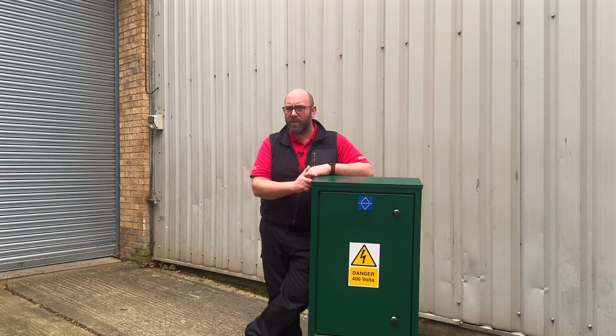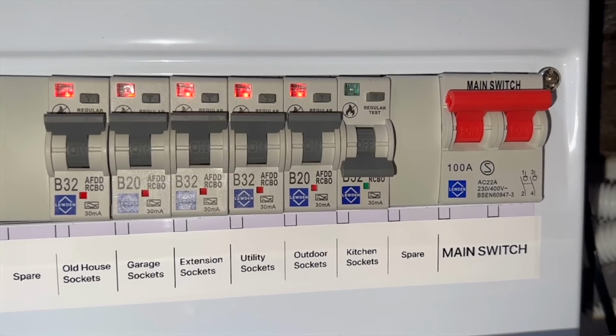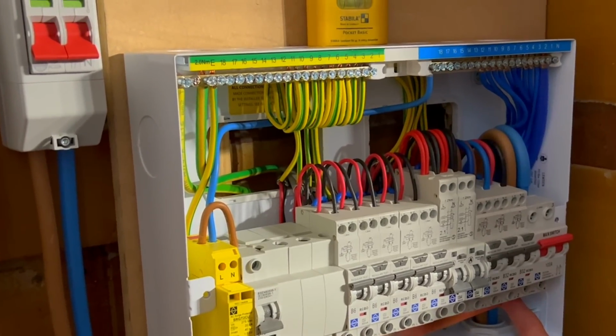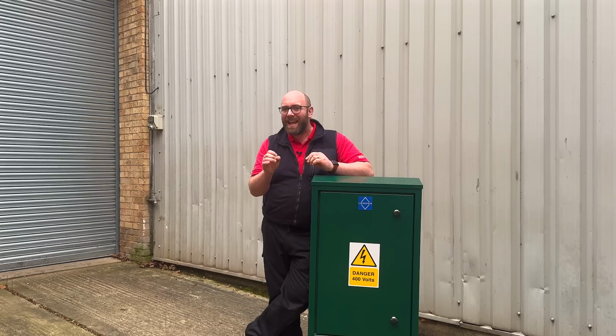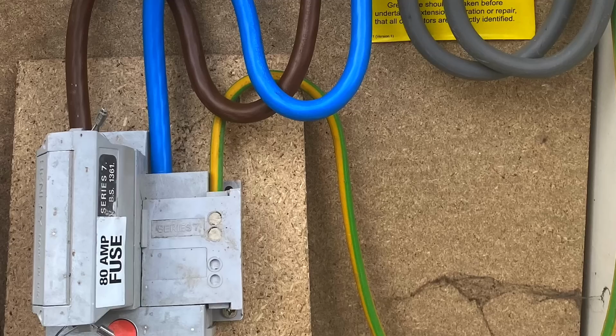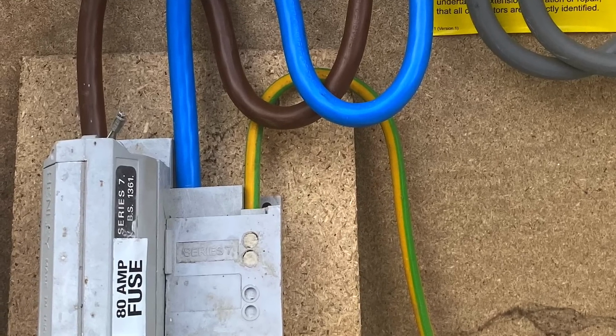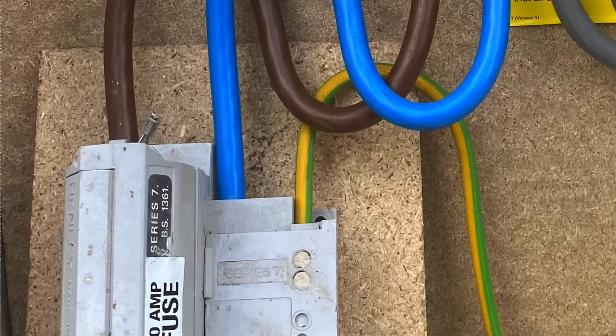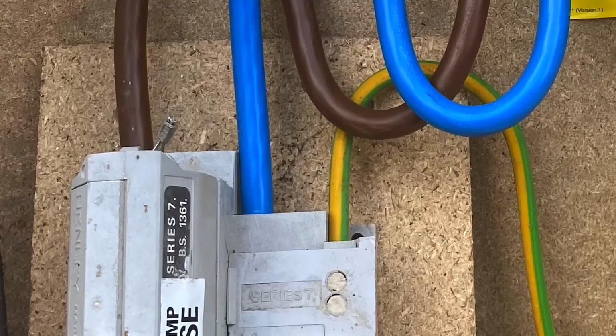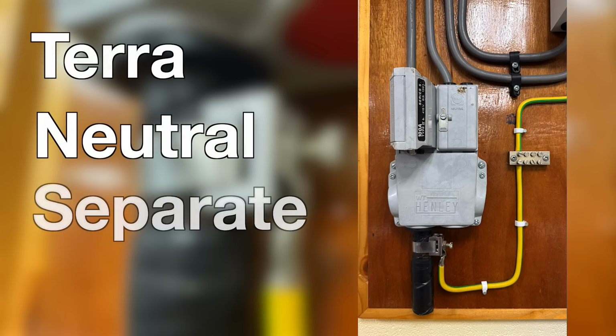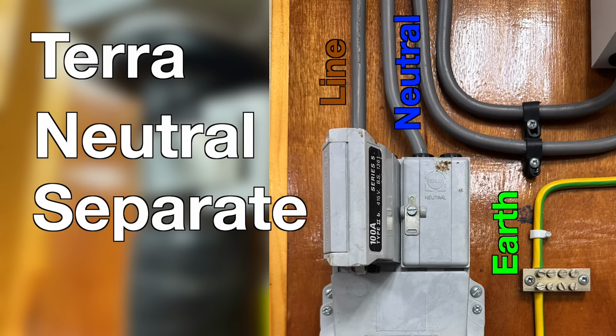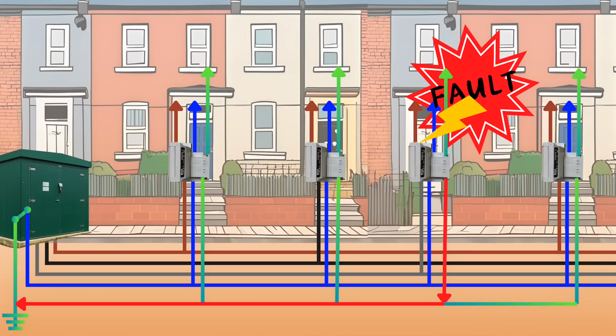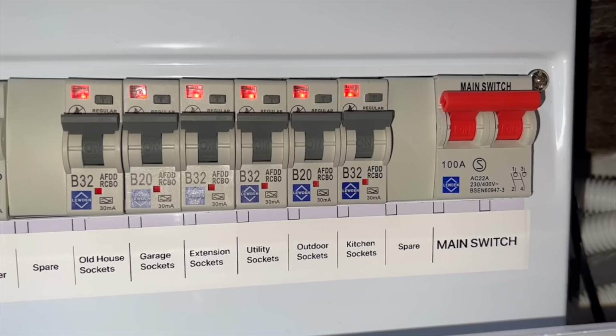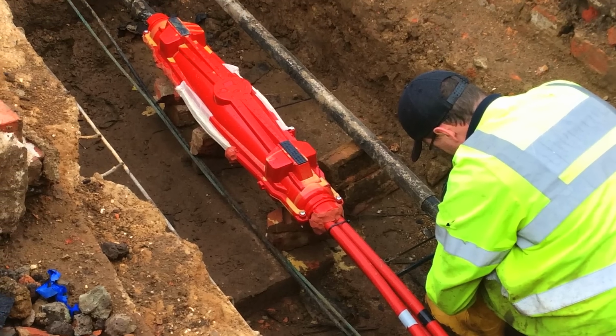This separation is crucial for safety because it ensures that any fault current can safely flow to earth without carrying a risk of running through the neutral. The TNCS system provides an efficient, effective way to protect homes and installations from electrical faults, maintaining safety whilst being cost-effective for distribution networks. The TNS system is a Terra Neutral Separate system, which has three distinct conductors: line, neutral and earth. This is an excellent system as fault currents can be distributed down a separate conductor to earth. However, with running in an additional conductor, this will increase the cost of the distribution cable.